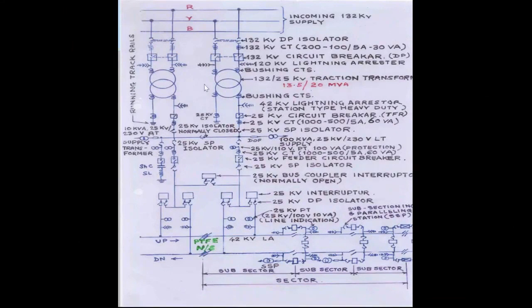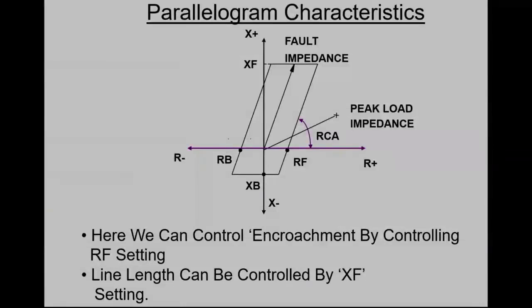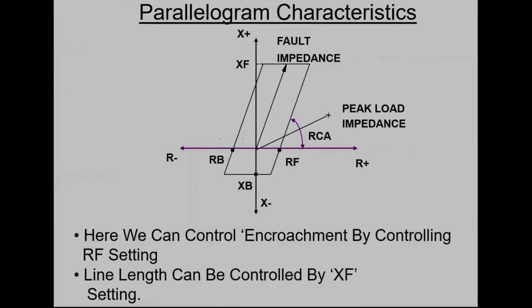So you can see the transformer is provided with unit protection, and this transmission line which is coming from this line to the transformer is provided with non-unit protection. The same concept which we discussed earlier, with characteristics such as the parallelogram characteristic. So this is very simple. This is the same as what we have seen in the previous example. If you recall, we spoke about Z = R + jX, and Z = V by I. We called Z = V by I the measured impedance, Zm, and Z = R + jX the set impedance.